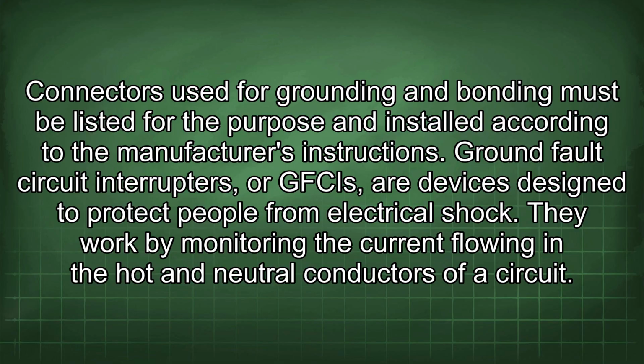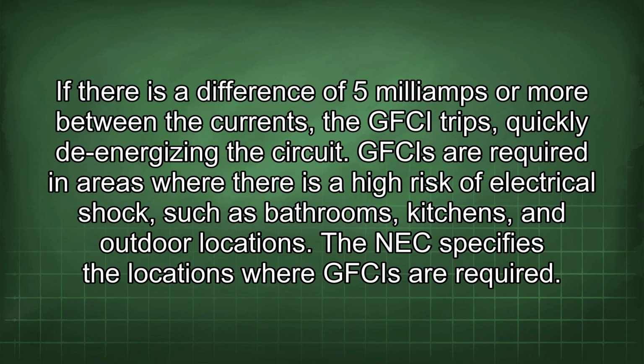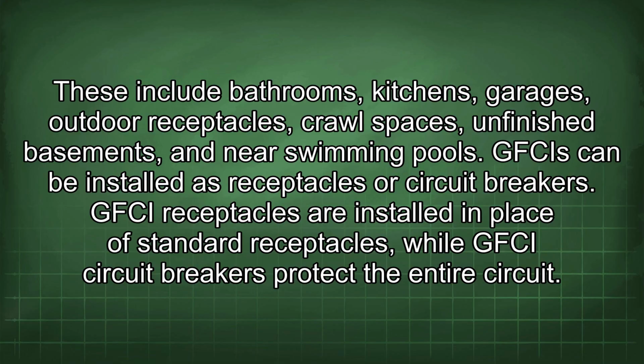Ground fault circuit interrupters, or GFCIs, are devices designed to protect people from electrical shock. They work by monitoring the current flowing in the hot and neutral conductors of a circuit. If there is a difference of 5 mA or more between the currents, the GFCI trips, quickly de-energizing the circuit. GFCIs are required in areas where there is a high risk of electrical shock, such as bathrooms, kitchens, and outdoor locations. The NEC specifies the locations where GFCIs are required. These include bathrooms, kitchens, garages, outdoor receptacles, crawl spaces, unfinished basements, and near swimming pools. GFCIs can be installed as receptacles or circuit breakers.